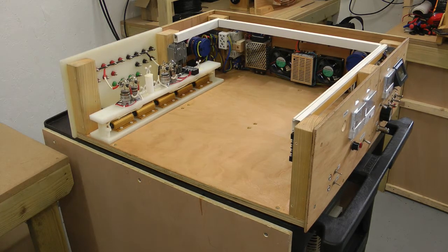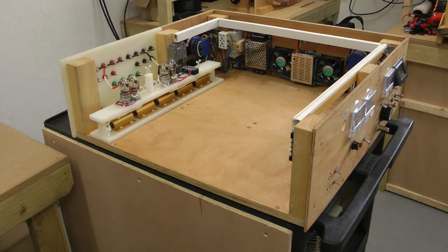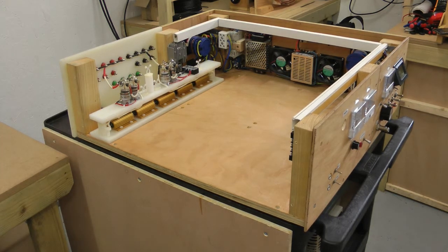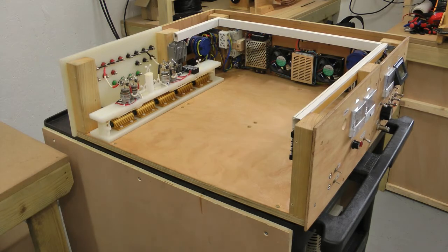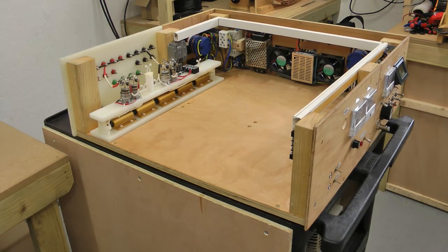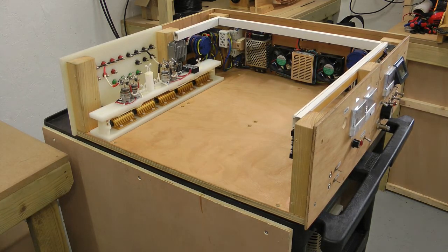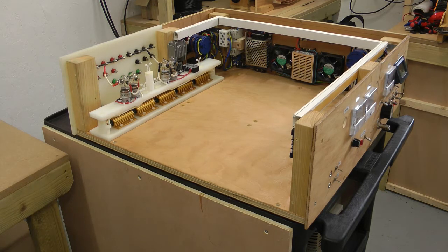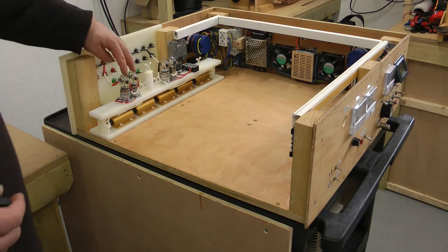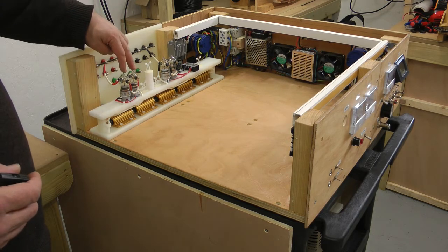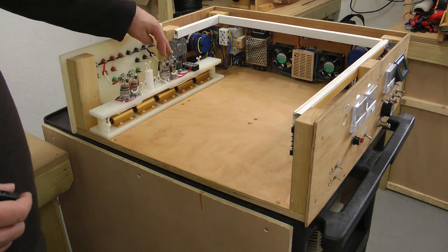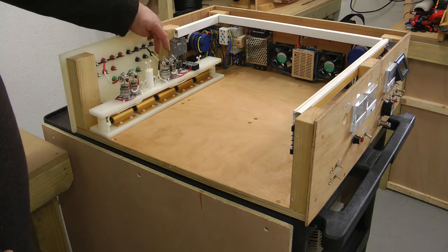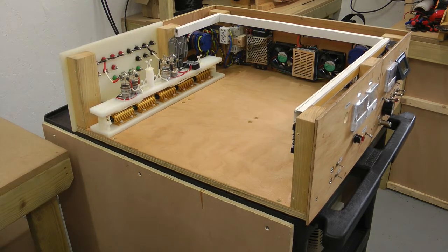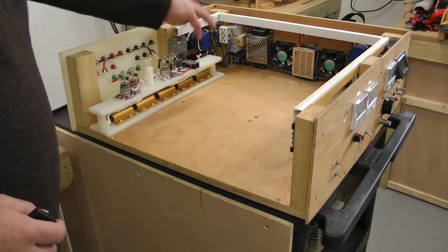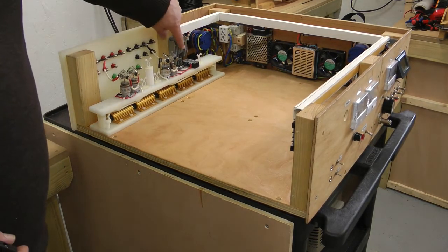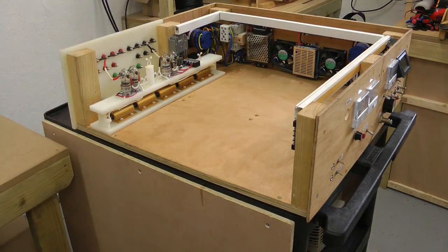vacuum relays. They're nominally 3 kilovolts at 10 amps, but I found them to be good for quite a bit more than that, particularly when it's just for a brief discharge. So 2 in series on the positive HT side, and 2 in series on the negative HT side. These are laced up and powered by the 24 volt module here on the low tension side.